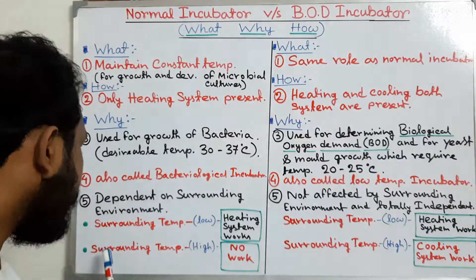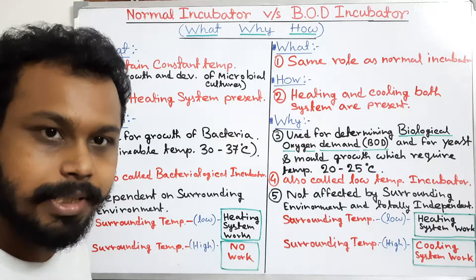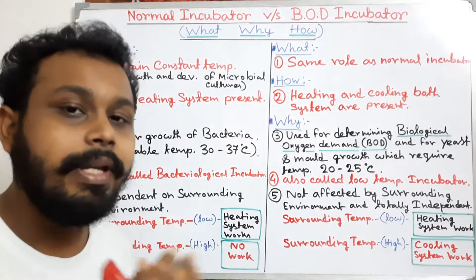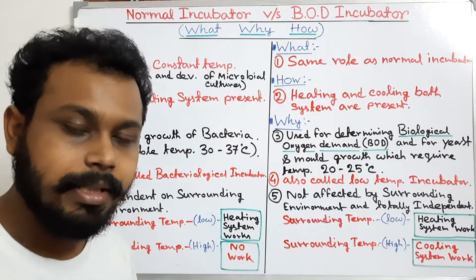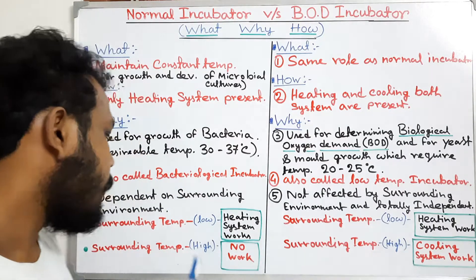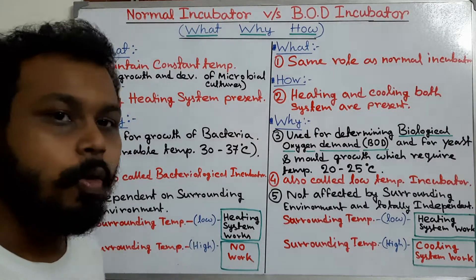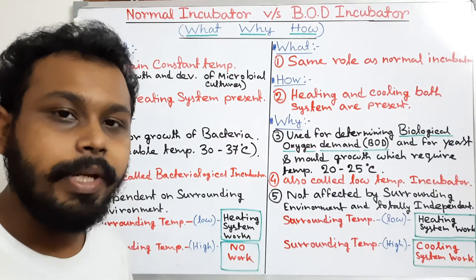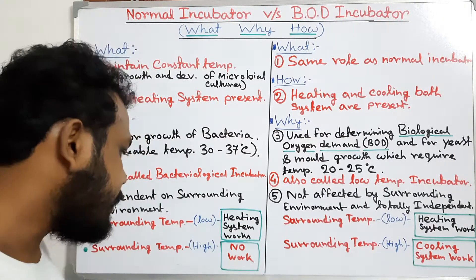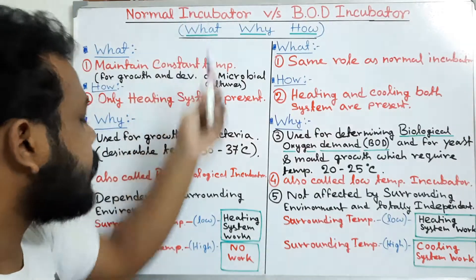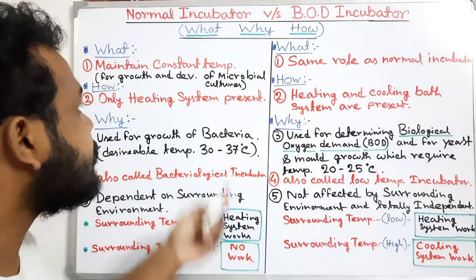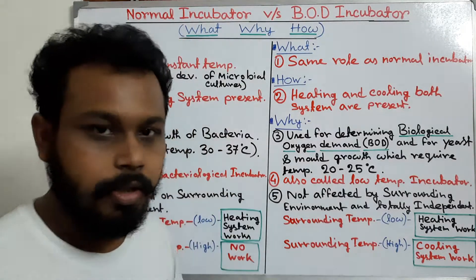However, if the surrounding or room temperature is higher than our setting temperature — for example, if we need 25°C but the room temperature is 30°C — the normal incubator cannot work because it has no cooling system. This is a disadvantage of the normal incubator.